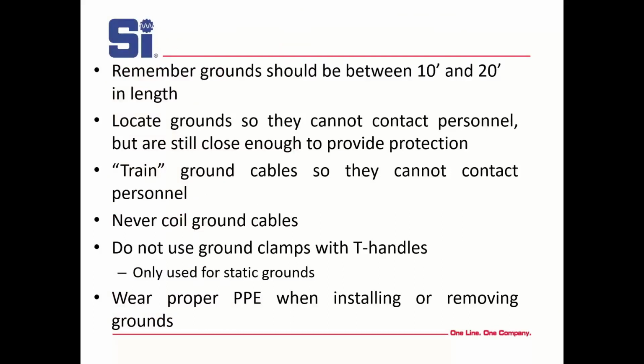Remember, ground cables should be between 10 and 20 feet in length. Absolutely locate them so they will not contact personnel. And when I say train the cable, if it's too long, wrap it around a post or something that will give it some support so it doesn't whip out. I know on YouTube, if you look at videos of grounds being shorted, man, those things whip. Never coil ground cables. That's an inductor. It's going to blow it up. Do not use ground clamps with T-handles. Those are static grounds. And wear proper PPE.